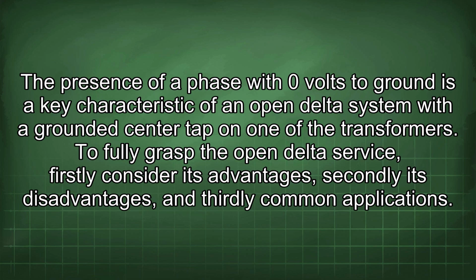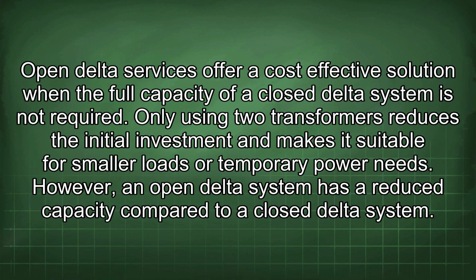To fully grasp the open delta service, firstly consider its advantages, secondly its disadvantages, and thirdly common applications. Open delta services offer a cost-effective solution when the full capacity of a closed delta system is not required. Only using two transformers reduces the initial investment and makes it suitable for smaller loads or temporary power needs.